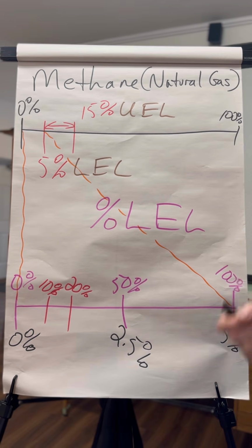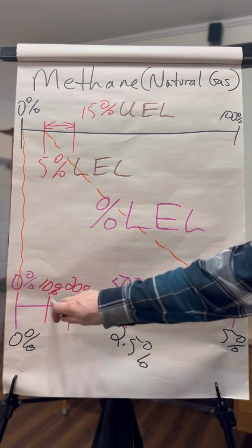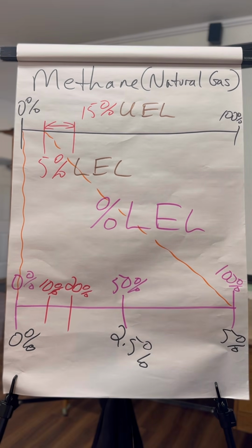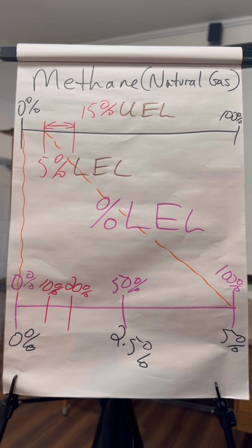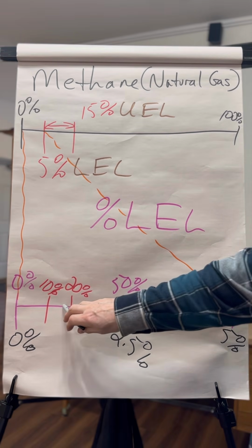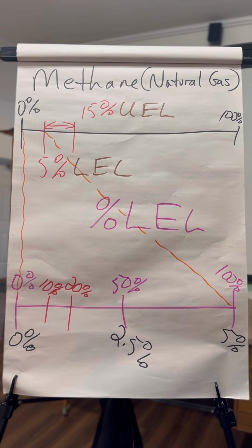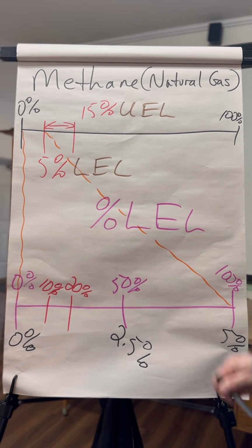So when you have a combustible gas monitor or an LEL monitor, it will have 2 alarm set points, 10% and 20%. So below 10%, you need continuous monitoring for hot work and cold work. Above 10%, you're not allowed to do any hot work, it's cold work only, while wearing a positive pressure SCBA or SABA. Above 20%, all work stops.